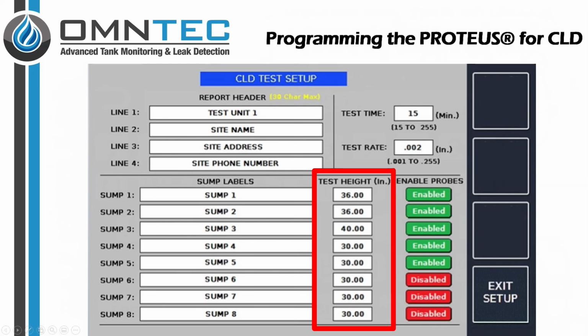Select test height to calibrate the measured height of the test liquid inside the sump. Use the keypad to enter the height of the test liquid. An example, 36 inches. The test height will now begin calibrating. Do not move the probe assembly until calibration has completed. Calibration is completed once the height matches the entered value. Programming can continue during calibration. Confirm that all entries are correct. Also verify that calibration matches the measured test height. Press Exit Setup to save your changes.